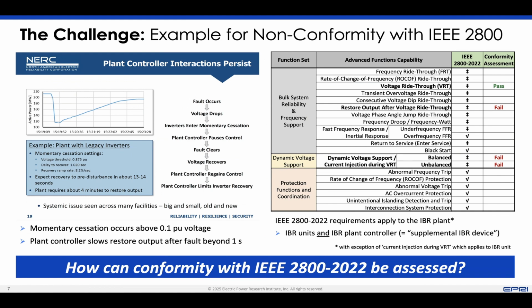Even though in this case the plant did ride through successfully, which is why it shows a pass on the voltage ride through, we could tell from the restoration of output power after the ride through that the plant did not, or would not have, conformed with IEEE 2800.